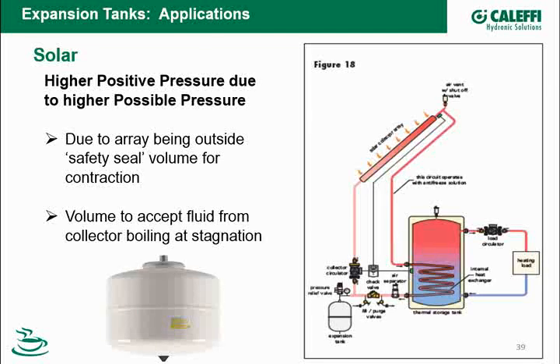Now, the final thing that also increases the size of the expansion tank in thermal solar applications is that most manufacturers will also look at the tank being large enough to accept the volume of the collector if the collector stagnates and the solar fluid does boil. Our solar panels hold anywhere from a gallon to a gallon and a half of fluid per panel. So if I look at the sizing procedure, which is a long formula in Hydronic 3, part of the sizing process is to size the fluid of the collector, and that becomes the baseline of the sizing of the expansion tank.